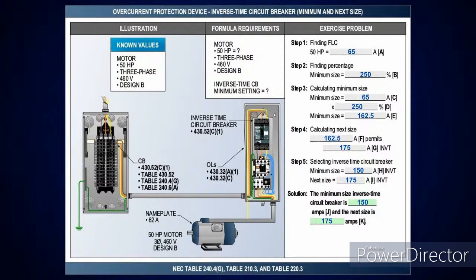And then you look here at the table for my inverse time, it tells you take it at 250. So I take 65 amps at 250%. That gives me 162.5 amps. The next size below that is a 150. And then if it won't start due to inrush current, I can just go up to the next standard size and put a 175 amp overcurrent device there. Okay? Now, when you look at that, that's not hard.